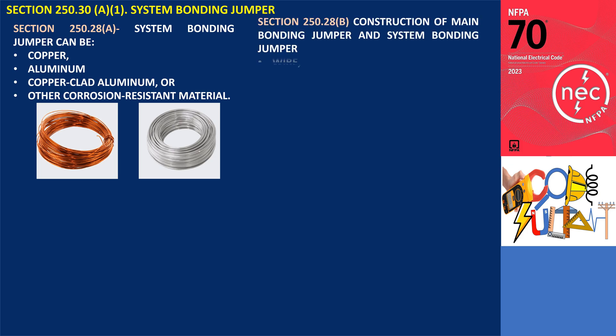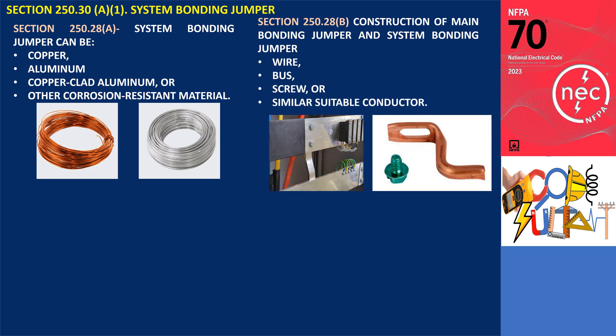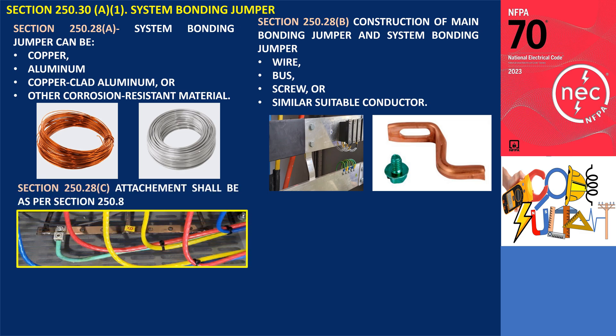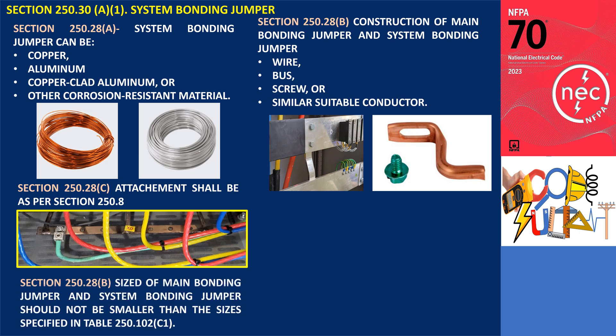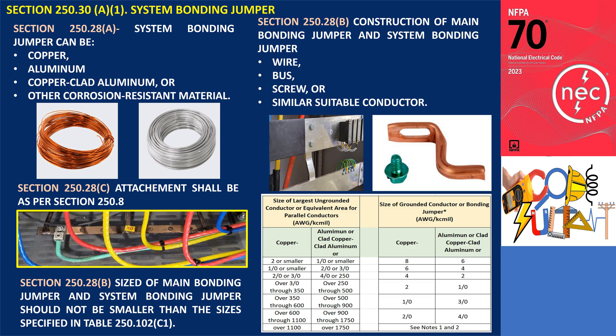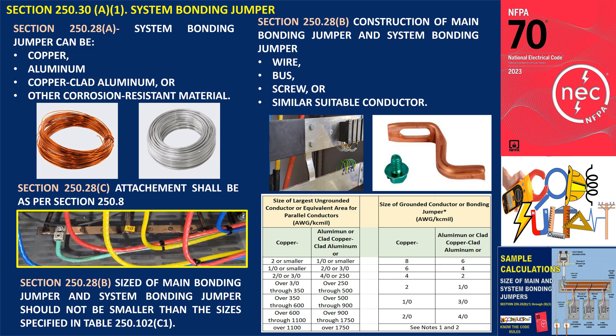The system bonding jumper construction can be in the form of a wire, bus, screw, or similar conductor, and the connection to the system bonding shall be made using the methods specified in section 250.8, such as terminal lugs or bars. The size of the system bonding conductor is selected from table 250.102.C.1, as specified in section 250.28 D. For sample sizing and calculation, you can refer to the previous video.